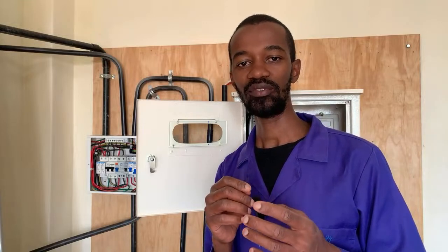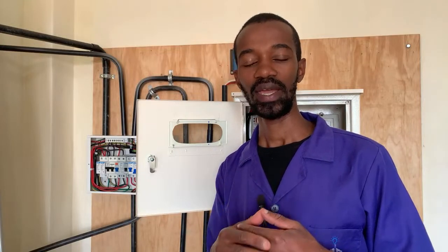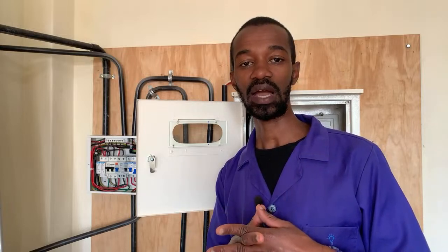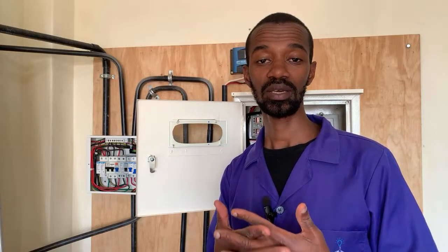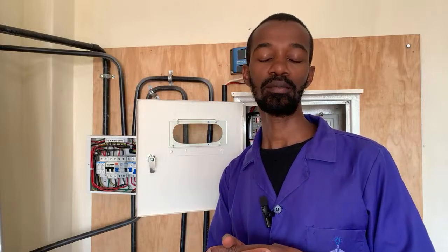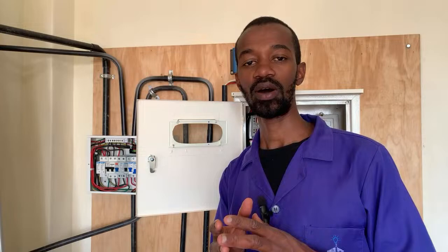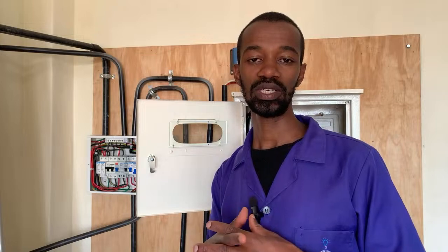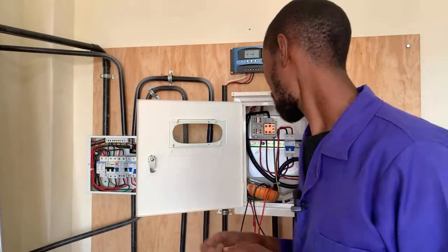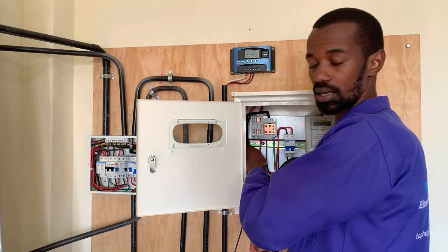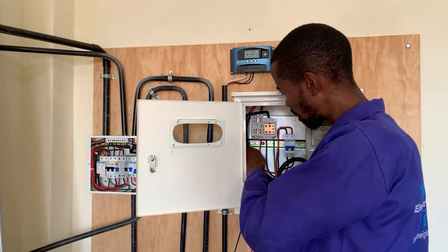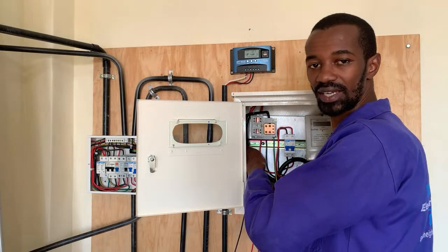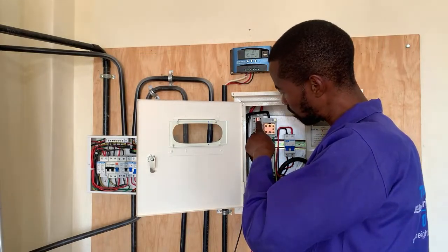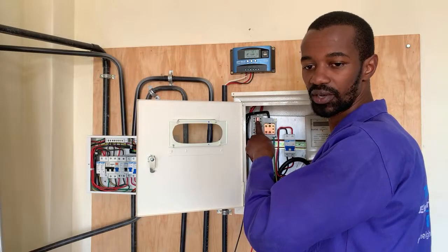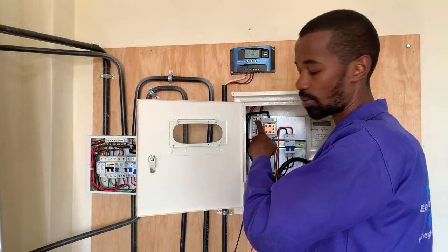So I will cut out the part that has burned, and if the cutout is not much affected, I'll still use the same cutout. If it is affected with a lot of burning, I'll have to buy a new quality one, and ensure that when connecting this drop cable back, I use the right tool for a tight connection, because loose connections will definitely lead to such a problem.